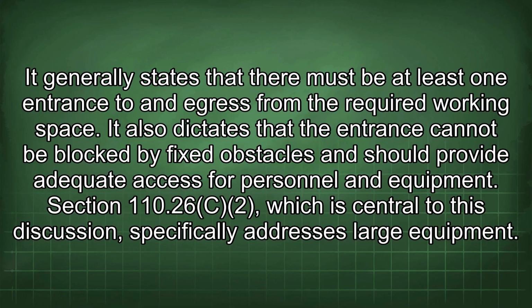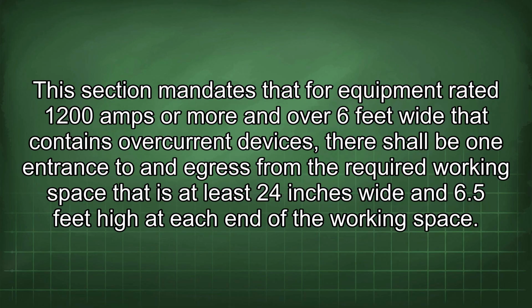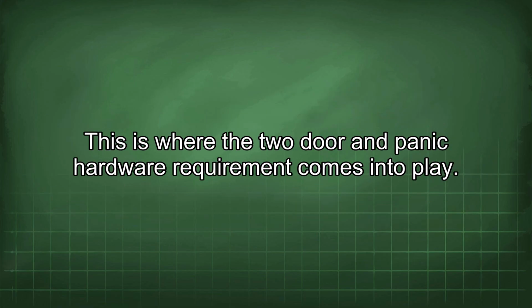Section 110.26C2, which is central to this discussion, specifically addresses large equipment. This section mandates that for equipment rated 1200 amps or more and over 6 feet wide that contains overcurrent devices, there shall be one entrance to and egress from the required working space that is at least 24 inches wide and 6.5 feet high at each end of the working space. This is where the two-door and panic hardware requirement comes into play.